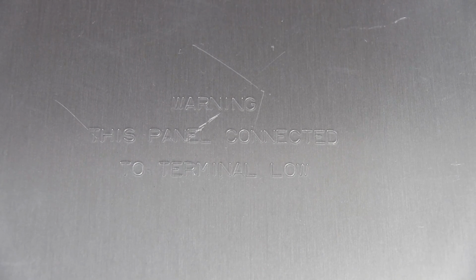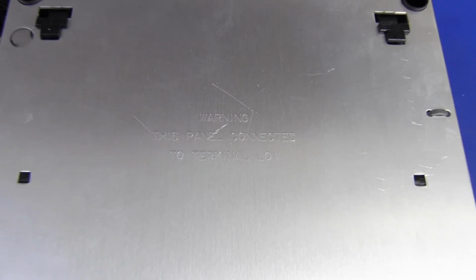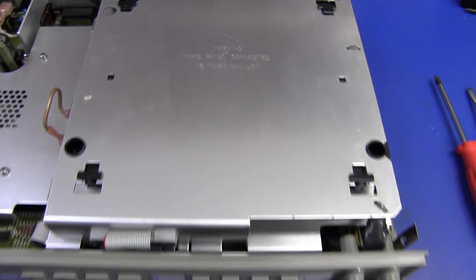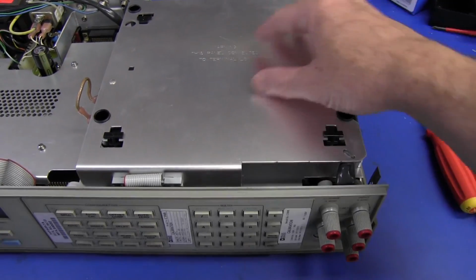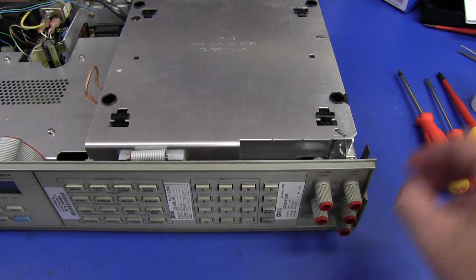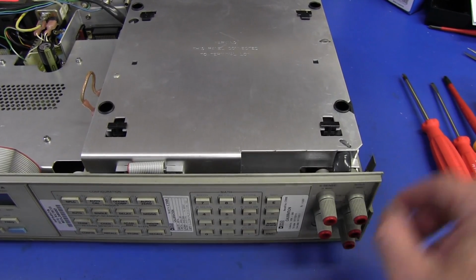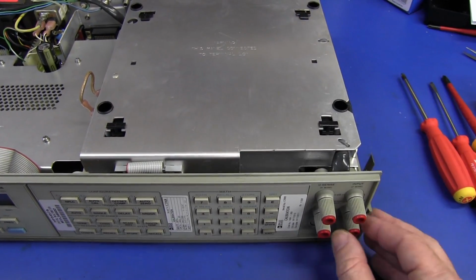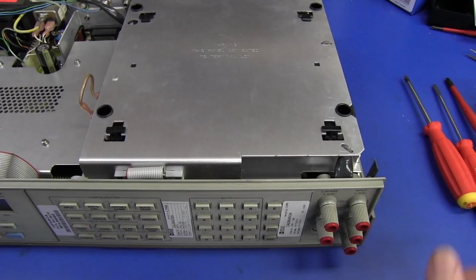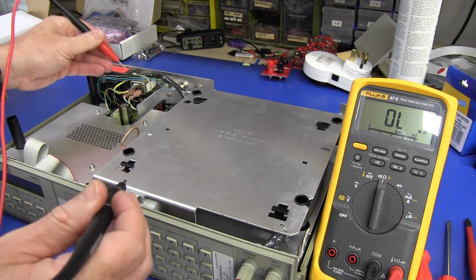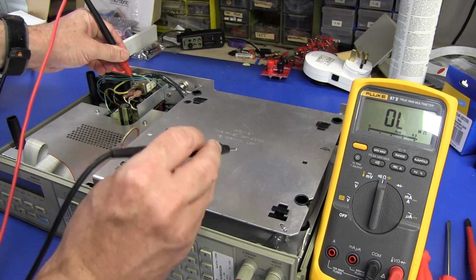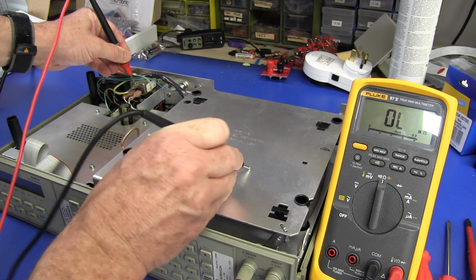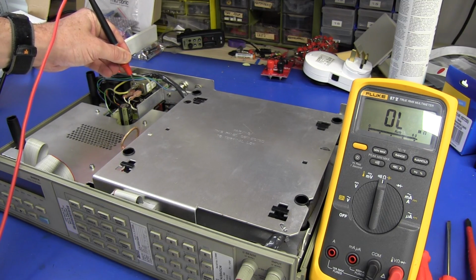Warning, this panel connected to terminal low, and that's not surprising at all. That internal shield there is connected to your ground. It's not connected to mains earth, it's just connected to the ground on the front panel. And we can verify that by mains earth there, and there we go. There's no connection whatsoever through to the ground terminal because of course it's floating.